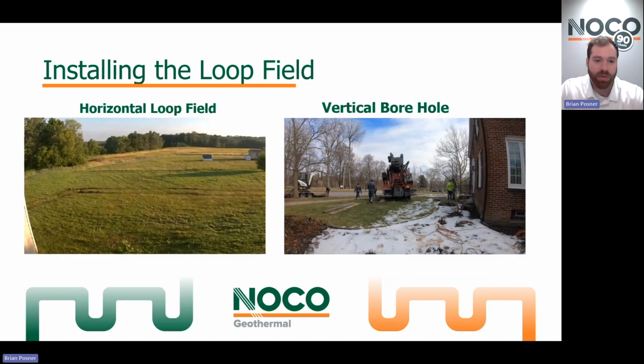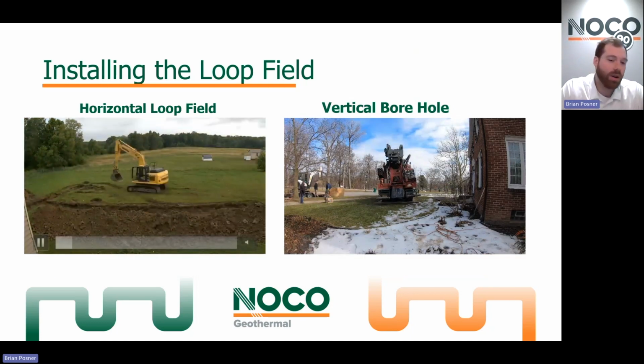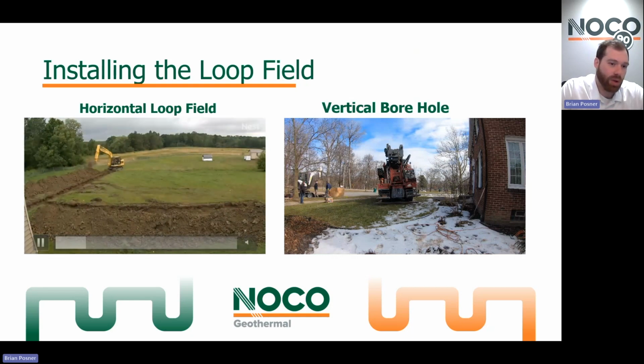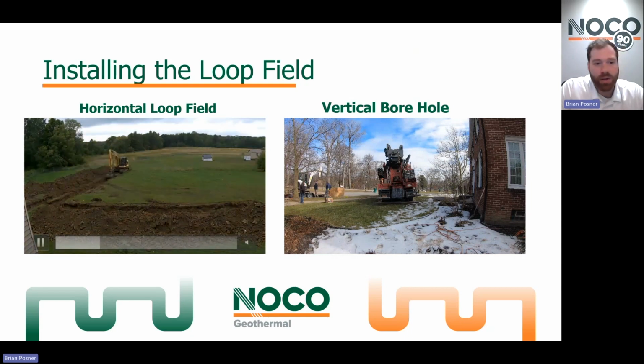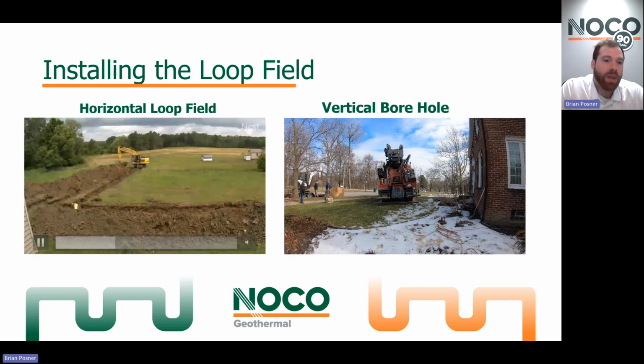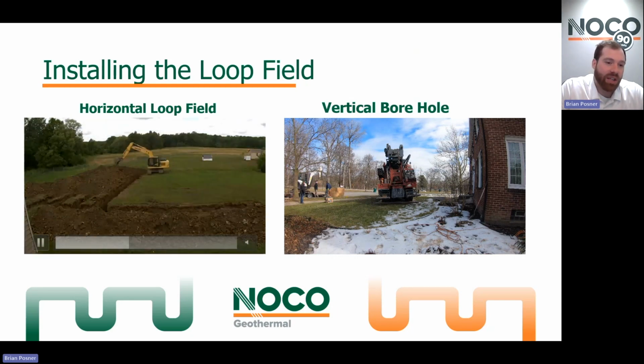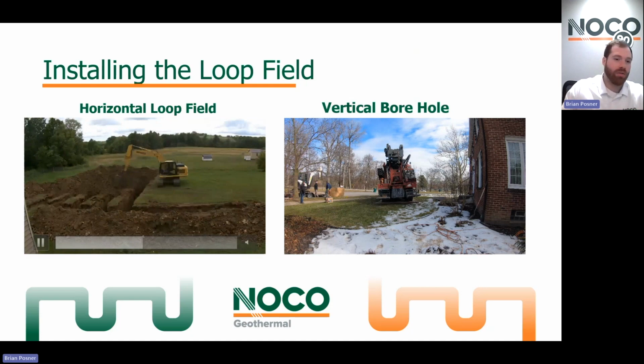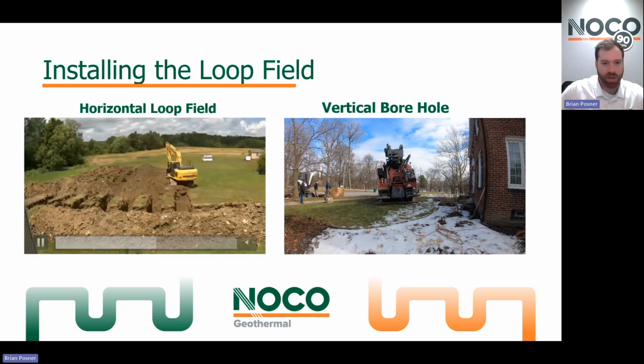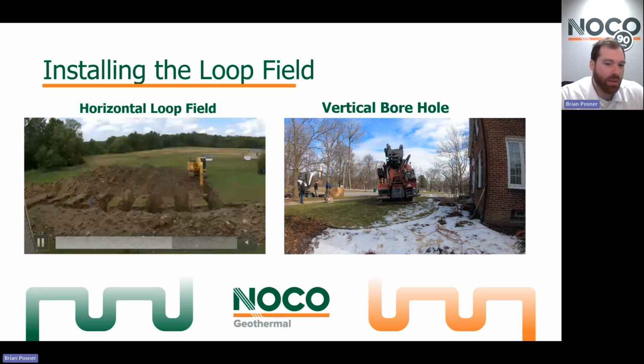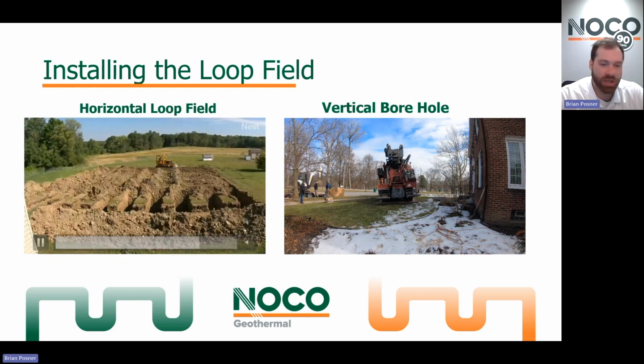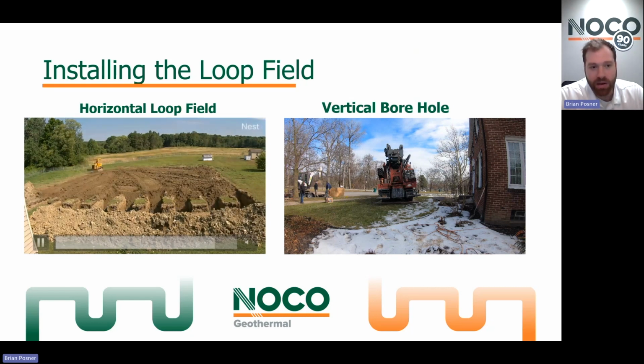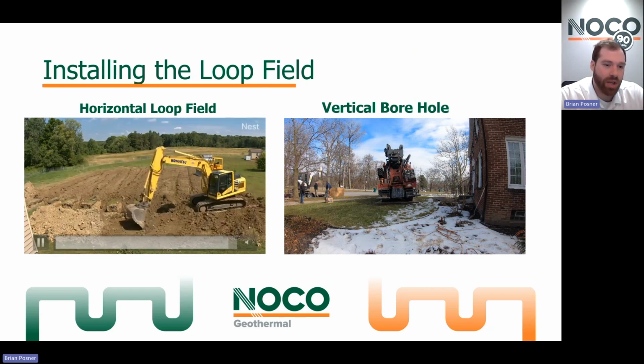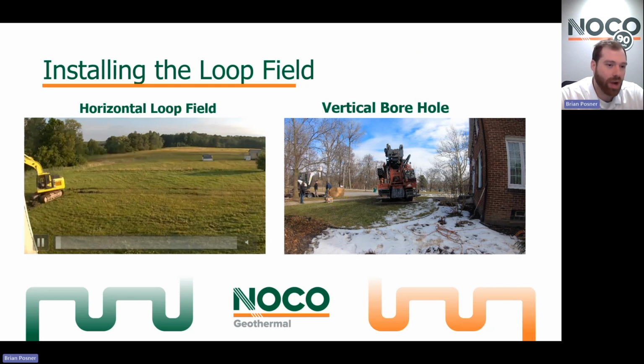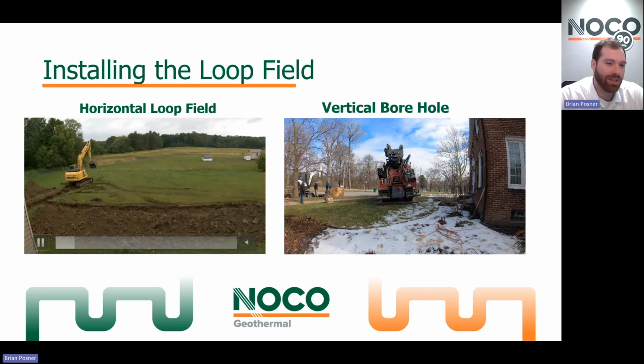So to give another example of how those go in, I have time lapses here of both the horizontal and the vertical borehole heat exchanger installs. On the left side, you can see this time lapse going. You can see as the excavator gets to the back of a trench, it looks like some people flash across the screen really quickly. What that is, is our guys coming over and dropping that 600-foot coil of piping into the bottom of those trenches. The minute they drop that piping in, the excavator starts digging the next trench and uses the earth he excavates from that next trench to backfill the one he had just dug.